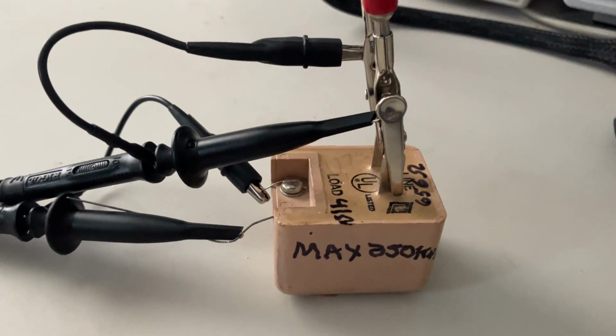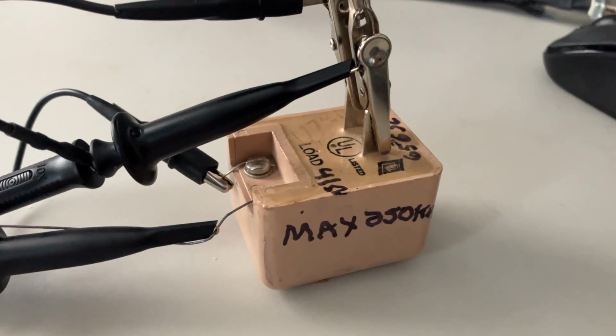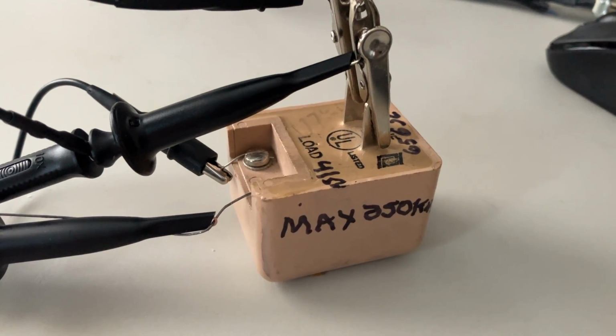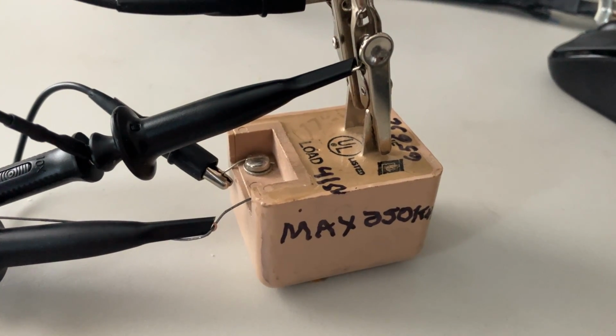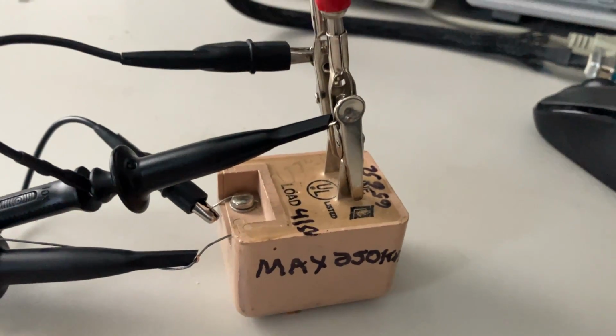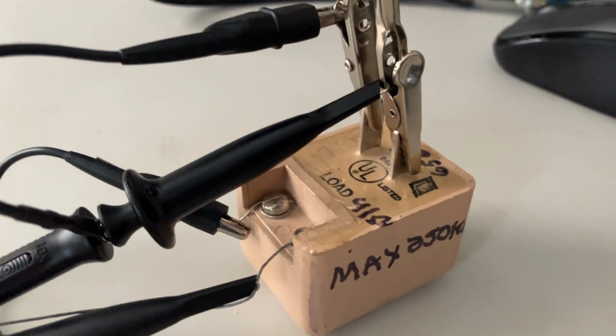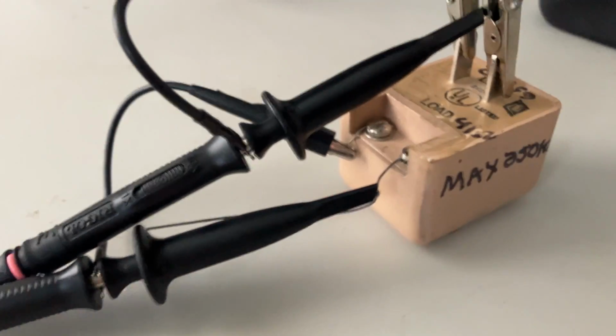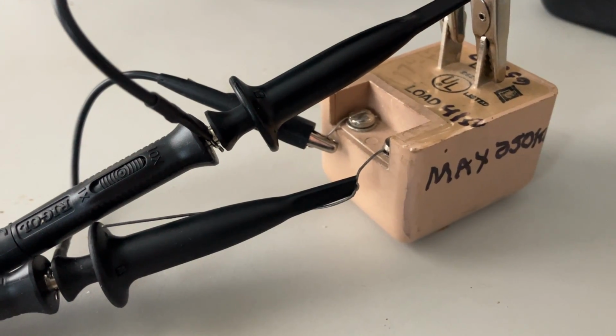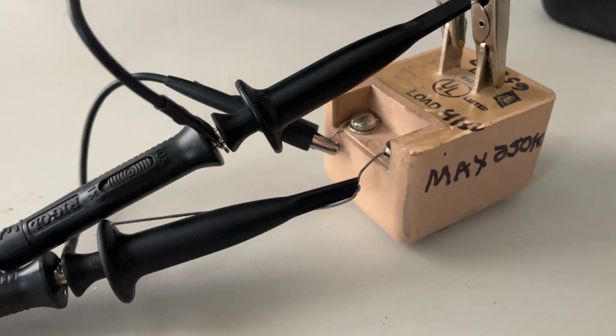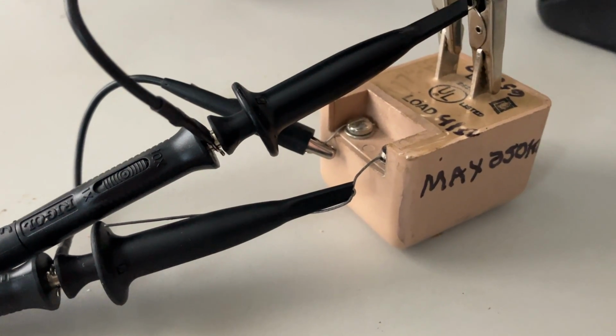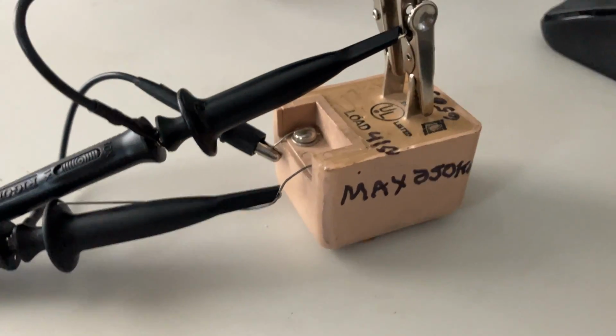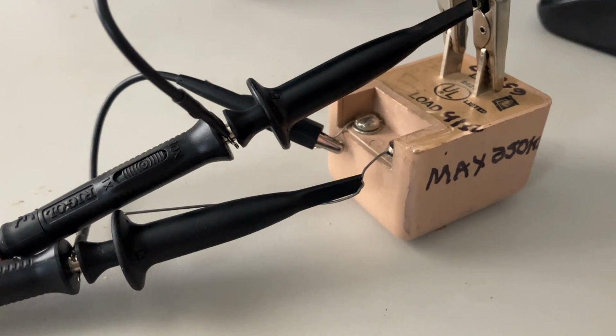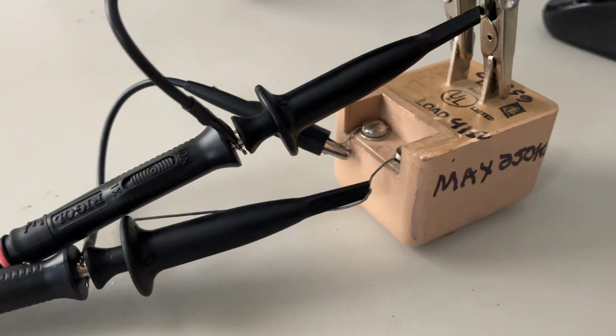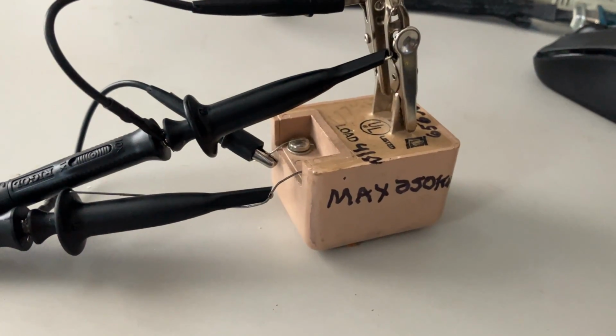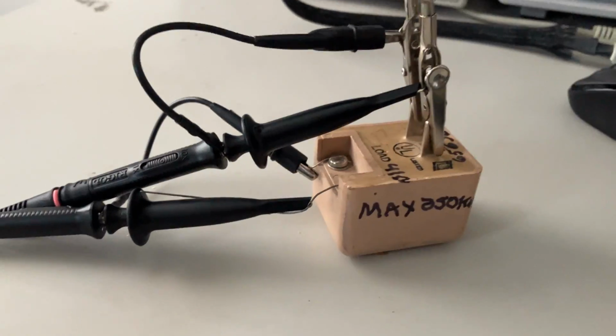So basically, when you use this for the Bode plot response of a switching power supply, you want to have high impedance injection of your frequency generator on the 110 volt, and the low impedance output that you collect in parallel with the 5 or 10 ohm that you modify on your circuit of your switching power supply on the other side. So that protects from the DC, that protects from the low impedance of the switching, so the switching signal does not go up to the other side because of the difference in the impedance. But it's a very nice circuit.